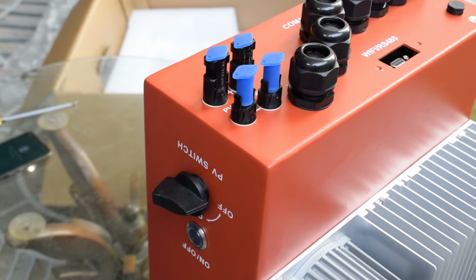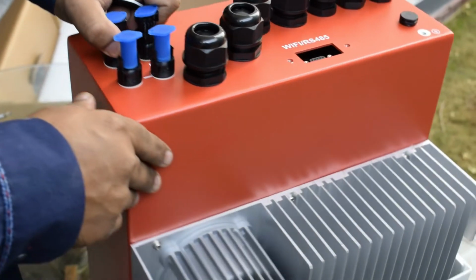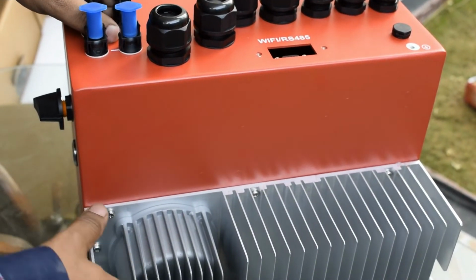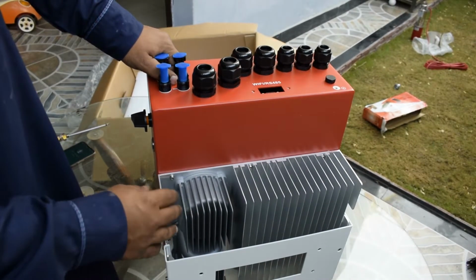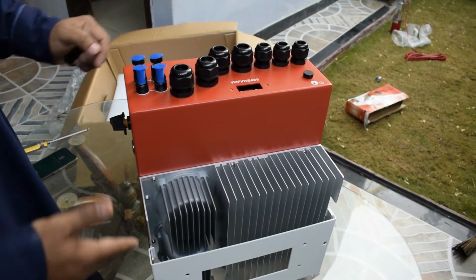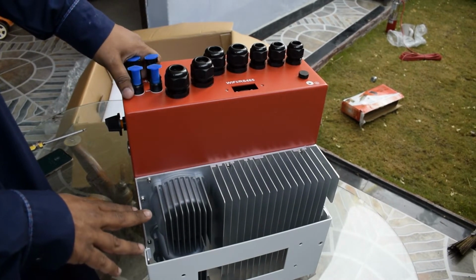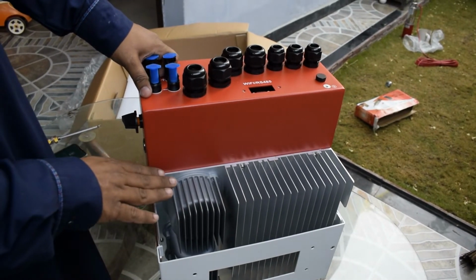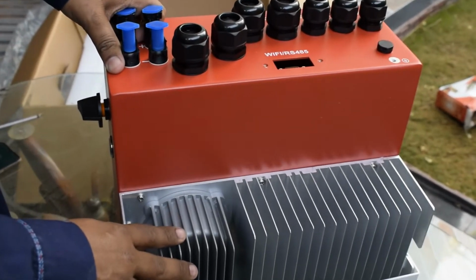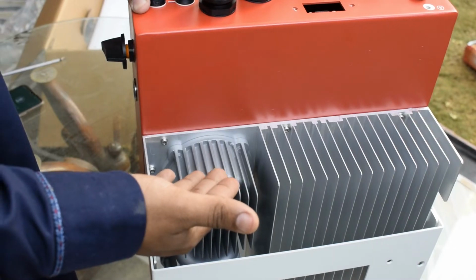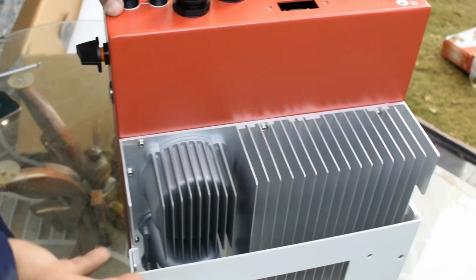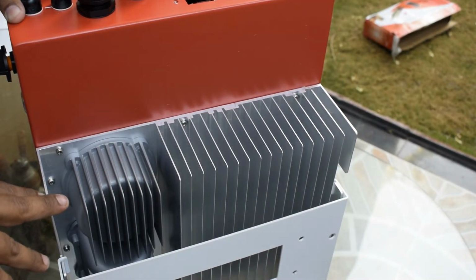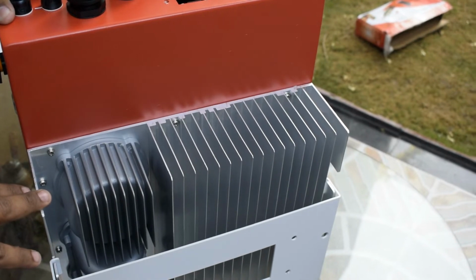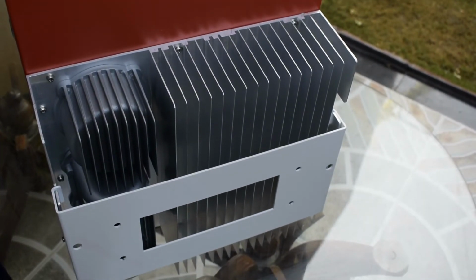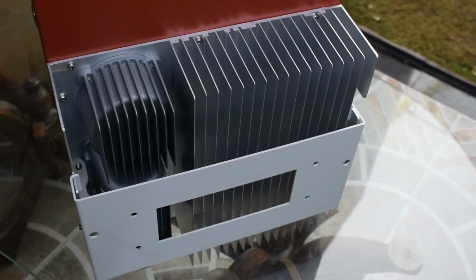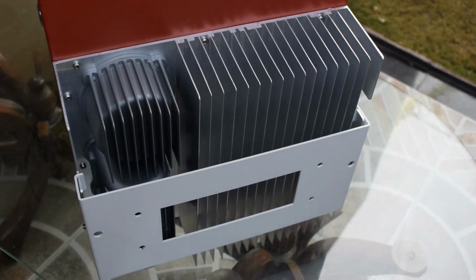The whole inverter is IP65, waterproof and dust proof. You can see the heat sinks. We don't have any fan operation over here. The fins are very large and extended, so the heat transfer from the fins heats up the air, the heat is carried away from the heat sink, and new fresh air comes into this place. So this is natural convection flow, and it's very beneficial and very energy efficient. We don't have any fan operation or any maintenance requirement in this inverter.